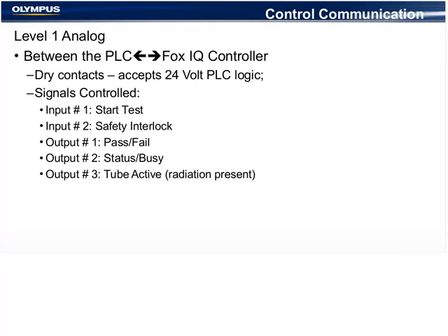Once we start communicating, we have two different options for communicating. The level one is the analog level. This is from the client's, the customer's PLC to the Fox IQ control box. We use dry contacts with a 24-volt signal from the PLC. And we're controlling just very basic signals. Start a test, safety interlock so that the controller for the plant can shut down our X-ray tube if it wants to. Output, pass, fail. We tell the PLC that we're busy when we're running a test, and we tell, for safety purposes, the PLC that the X-ray tube is active.